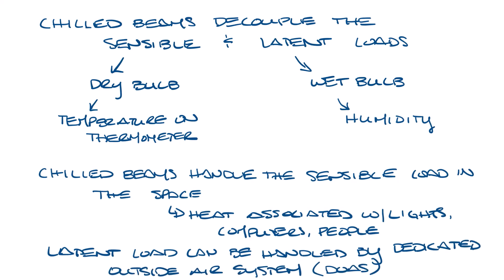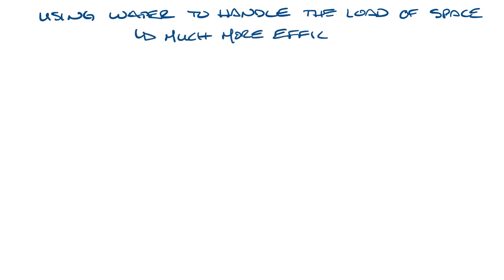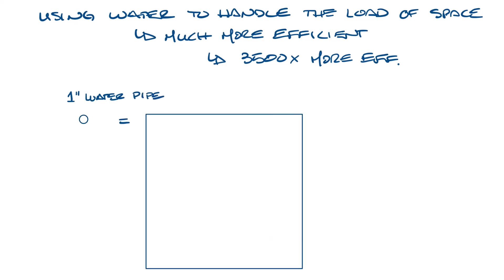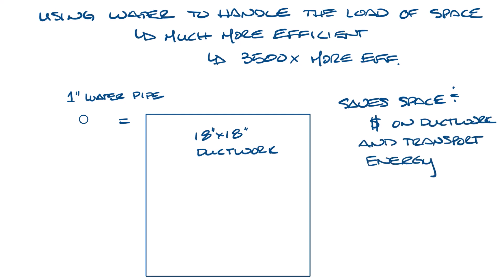One big benefit to doing this is that you're using water to handle the space load, and water is a much more efficient way to transfer energy. Water is almost 3,500 times as efficient when it comes to heat transfer. A one-inch water pipe can transport the same heating and cooling capacities as an 18 by 18 inch air duct. This huge difference means that you can cool the space using piping that's one inch instead of running larger ductwork throughout your building. This will save space and money on ductwork and the transportation energy, such as the fans that are required to push the air through that ductwork.